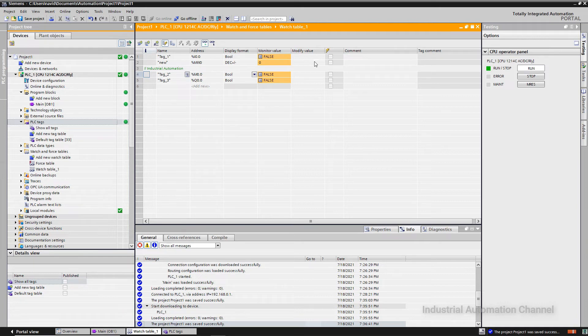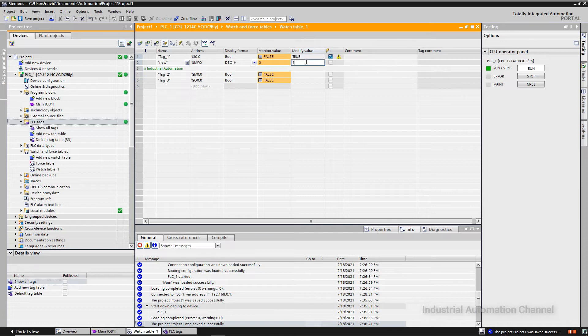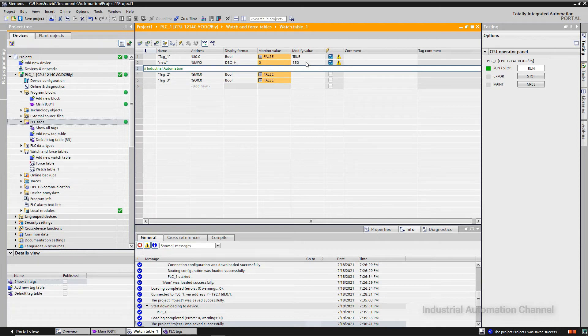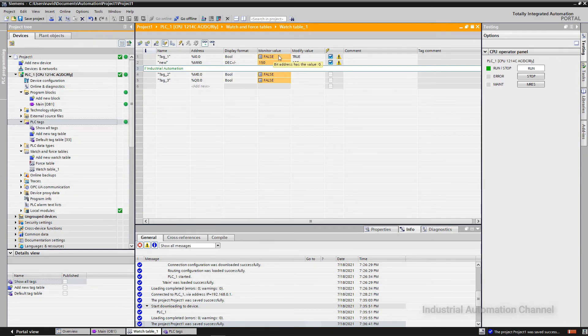When modify is active, there are two columns that we use to change our variables. I type 'true' for the input and 150 for the integer value, then press enter. You can see the checkbox in the second column is now activated. It says these addresses are not yet modified, although you have written 'true' or 150 in the first column. To modify selected variables, click on 'modify selected values once and now.' This will modify all selected addresses — the integer value is now 150 but the input is not yet true.